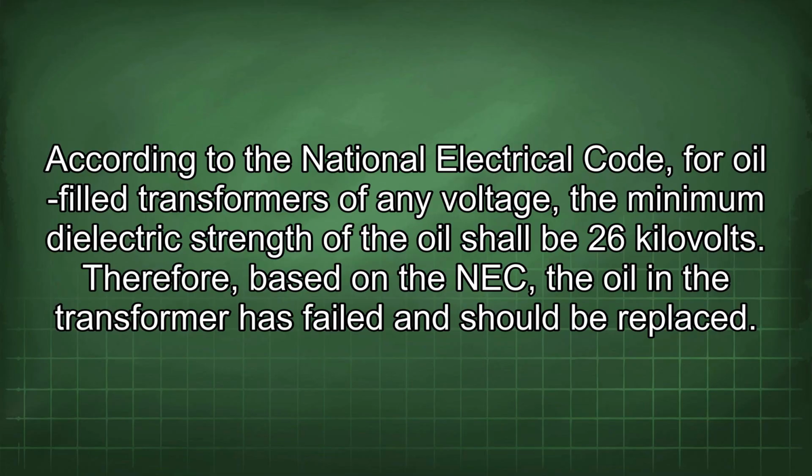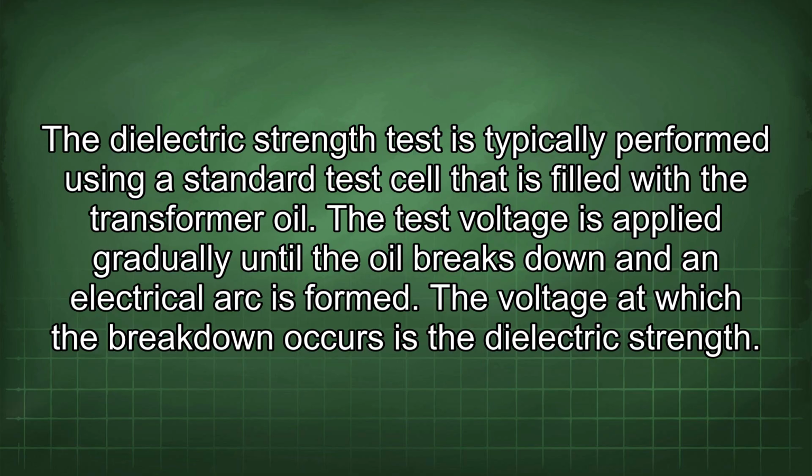According to the National Electrical Code, for oil-filled transformers of any voltage, the minimum dielectric strength of the oil shall be 26 kilovolts. Therefore, based on the NEC, the oil in the transformer has failed and should be replaced. The dielectric strength test is typically performed using a standard test cell that is filled with the transformer oil. The test voltage is applied gradually until the oil breaks down and an electrical arc is formed.